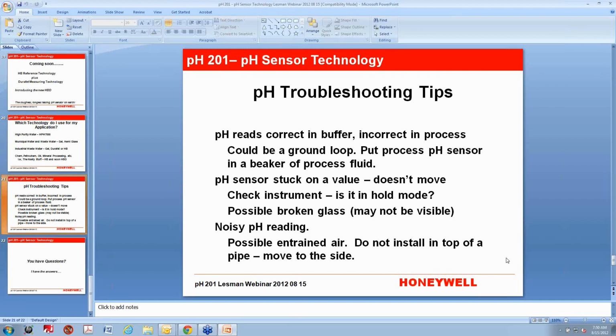Noisy pH readings. Noisy pH readings are oftentimes caused by entrained air. Lots of processes have air bubbles in them. It's pretty common. And air bubbles, because they're lighter than the rest of the process, will float to the top. So as a matter of course, you don't want to install a pH sensor, say, at the 12 o'clock position. If you're in a horizontal pipe, and you think of it as a clock, the top is 12. If you install the pH sensor directly in the top, and you have entrained air, all those bubbles are rising to the surface, and you can't measure the pH of a vapor or of air. You have to be in a liquid with these devices. And what it does is it gives a no signal pH signal. So what you see is the pH jumping all around because it's trying to measure air and it can't.